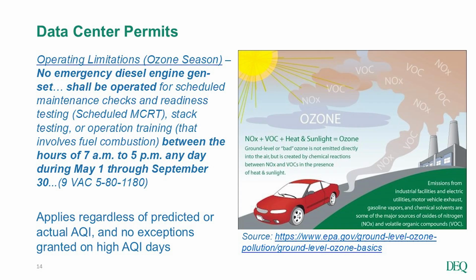Now talking a little about the content of our data center permits. One thing we put in place, particularly in Northern Virginia data center permits, is the requirement that when the facility operates their emergency gensets for maintenance and readiness testing, they only do that — at least during ozone season — during periods when temperatures are lowest, meaning at night. So we restrict them from doing that between 7 a.m. and 5 p.m. during ozone season, which runs from May 1st to September 30th.